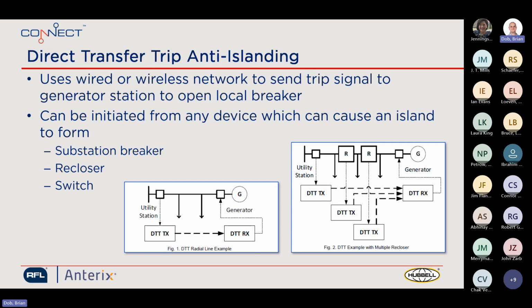For direct transfer trip, this is a pretty straightforward application. It uses some sort of communication network. This could be a wired system. It could be a wireless system. And the goal, of course, is to send a trip signal from the utility station to the generator and prevent that generator from backfeeding power. This could be by opening the point of common coupling, for example, between the generator and the utility grid or distribution circuit.